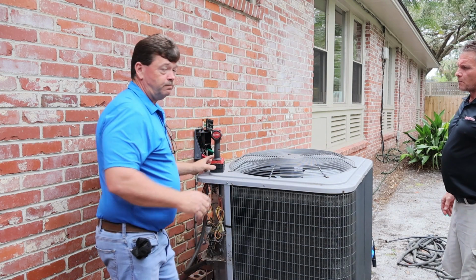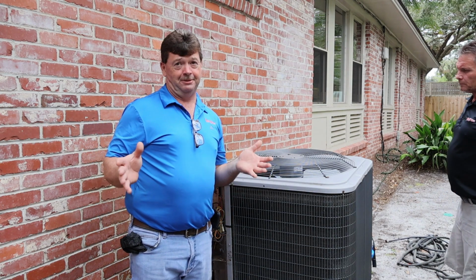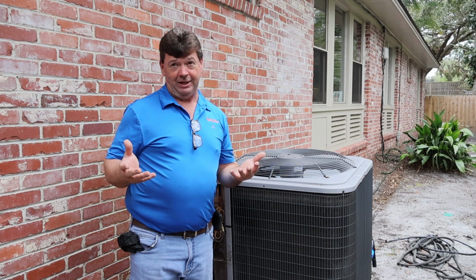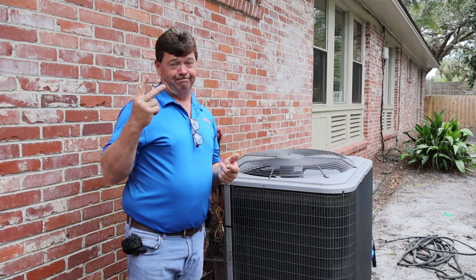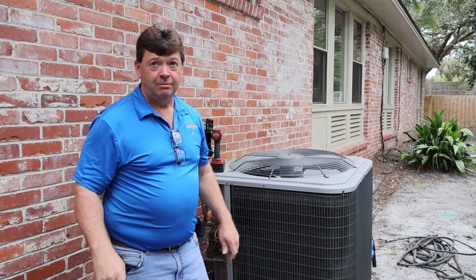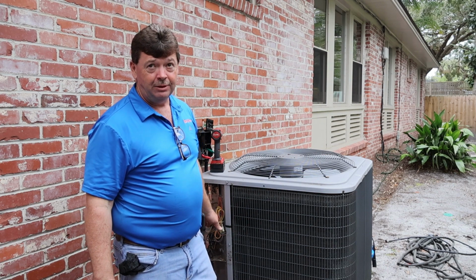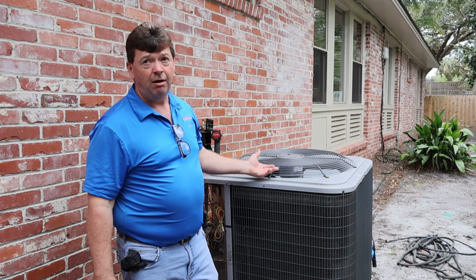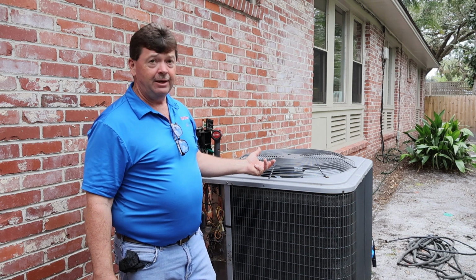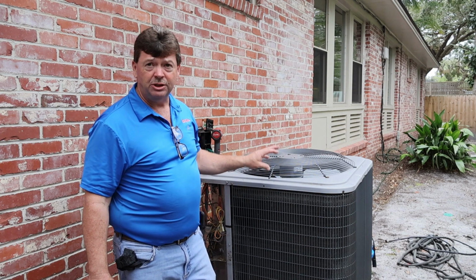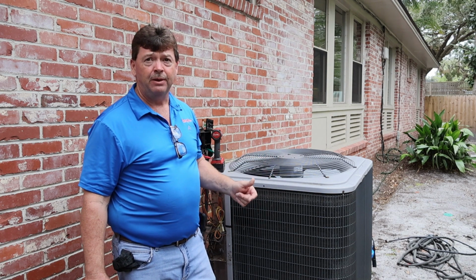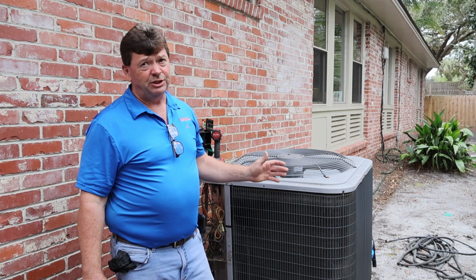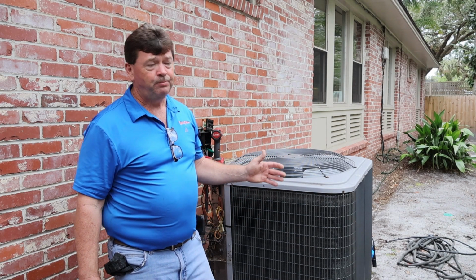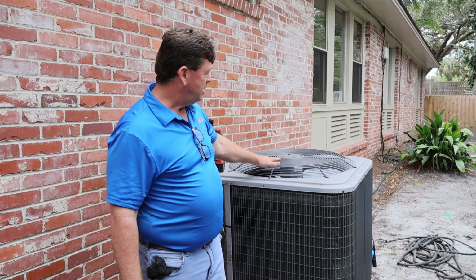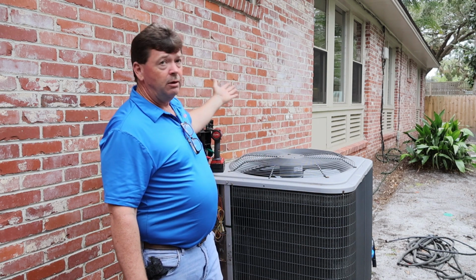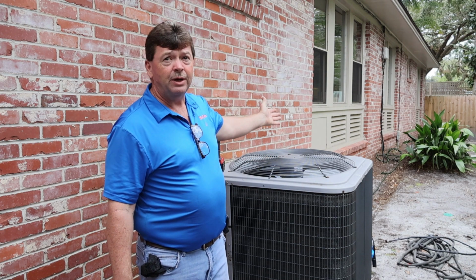Now, this is one of these things that if you're a service tech, you have two options here. You can unplug the wiring, take the top completely off, and then clean the leaves, wash the condenser coil from the inside out. The other option, which is sometimes a little more challenging, is if you can prop this top up out of the way where you don't have to take it off, that's okay too.